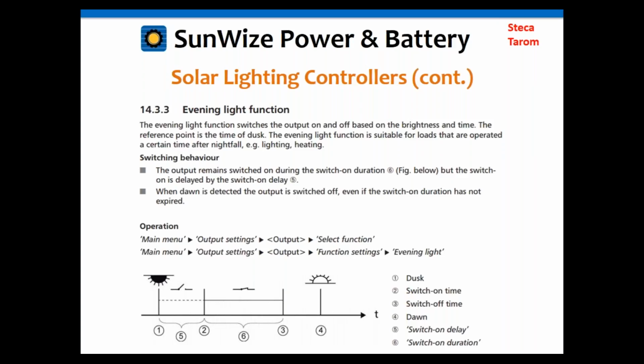So you'll see here the next function that it has is an evening light function. Basically you're able to control all the parameters shown on the bottom. So you'll have the dusk event, and then in 5 you'll have the switch on delay, which controls an amount of time that it delays the light to come on after dusk. Perhaps you don't want the light to come on for 2 hours afterwards. Then you can set the switch on time, that's number 2. And then you control the load switch on duration, which is number 6. You can see from the contactor icon above that the switch is closed and the load is on. And then 3, you basically have your switch off time, and then 4, you have your dawn. So again, that same sort of general structure, formatting your program control times and logic around the dawn and dusk.